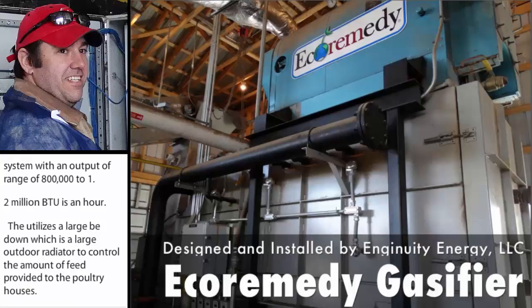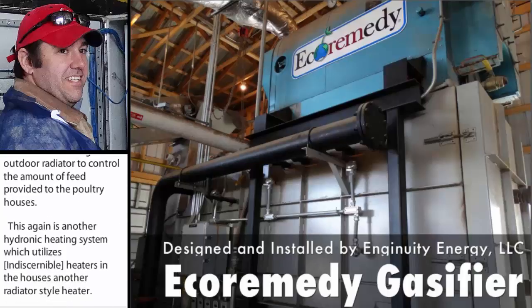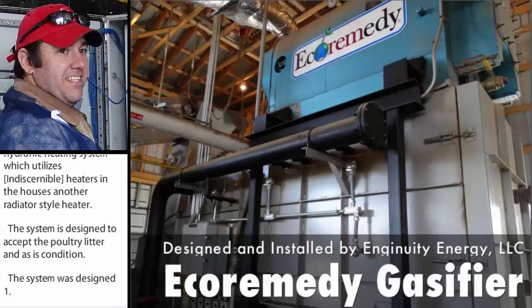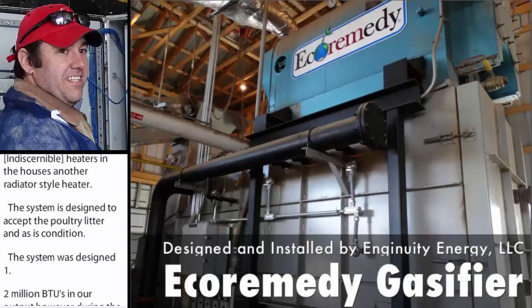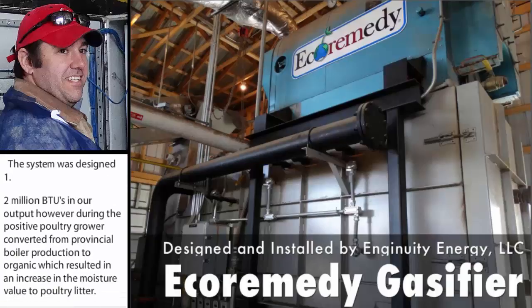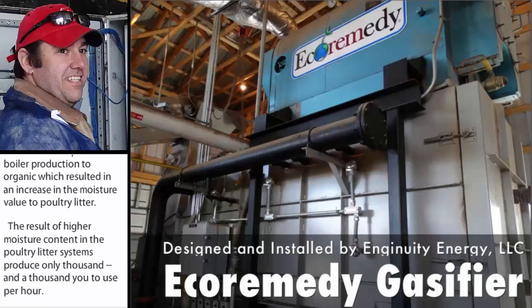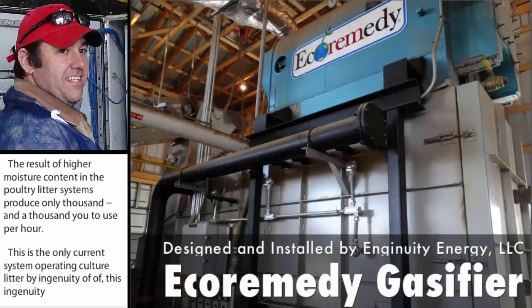This system is designed to accept poultry litter in the as-is condition. This system was designed for 1.2 million BTUs an hour output. However, during the project, the poultry broiler converted from conventional broiler production to organic, which resulted in an increase in the moisture value of the poultry litter. As a result of higher moisture content, the system is currently producing only 800,000 BTUs per hour. This is the only current system operating on poultry litter by Enginuity. This is the second Enginuity unit using manure as fuel in the U.S. Both units were installed at about the same time. This current system only has one winter flock of operation time. It also uses cyclones to control particulate matter.